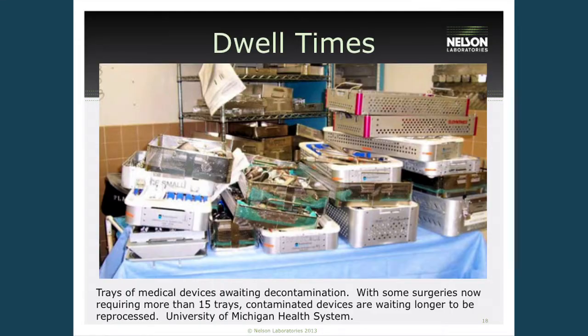Now, the central servicing people were stating that there is no way that all medical devices all the time stay wet. Sometimes they dry out when we have cases like this. So now the FDA is requiring a lot of medical device companies to test worst case scenario and to make sure that the contamination is fully dried onto the devices. This is causing a lot of issues with medical device companies because their normal procedures for cleaning aren't sufficient anymore because the soil is fully dried onto the devices. So that's one issue that we kind of go back and forth on.